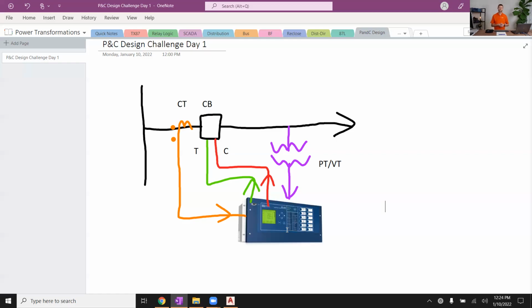We used to use electromechanical relays in earlier generations with moving parts and discs and coiled springs, et cetera. We're not going to really get into those in this course. We're going to focus on the modern day state of the art with microprocessor relays. Nowadays, you use a computer program to send settings to a microprocessor relay. Again, we're not covering the settings side in this course, but I know a lot of P&C design engineers who are very familiar with how to do all the designs, but what goes on inside the relay box is kind of a nebulous mystery. It's like a black box. If that's you, I encourage you to check out some of my previous courses where we go into those details of the different protective elements, the setting side, what goes inside the box. But in this course, we're focusing on the inputs and the outputs from this relay.